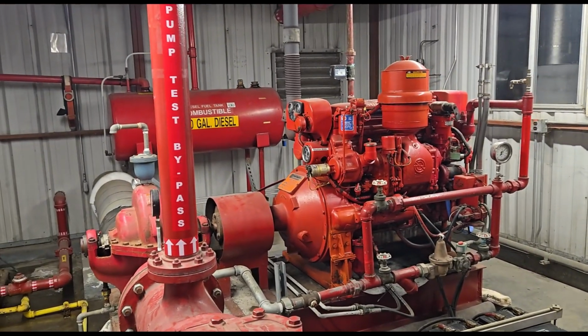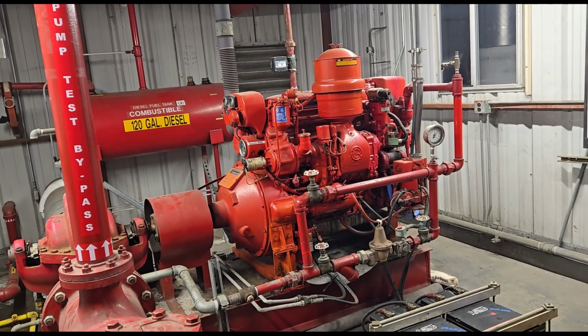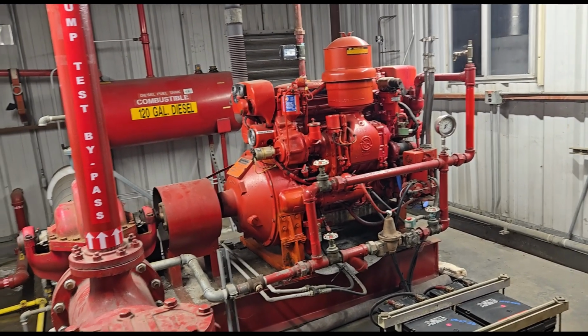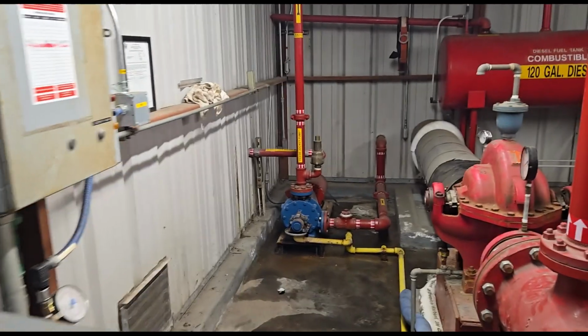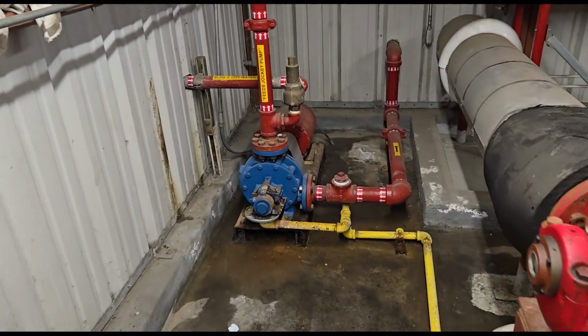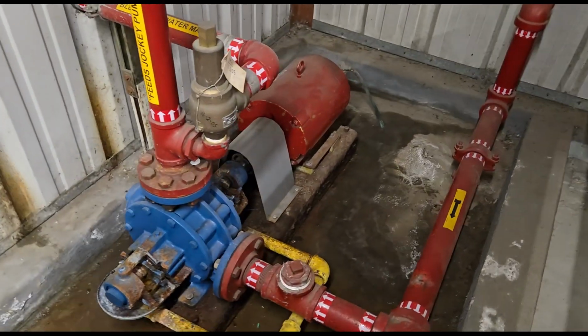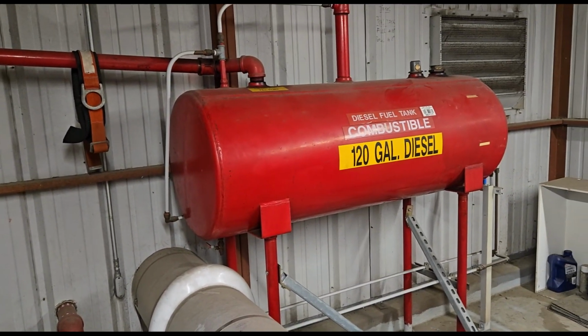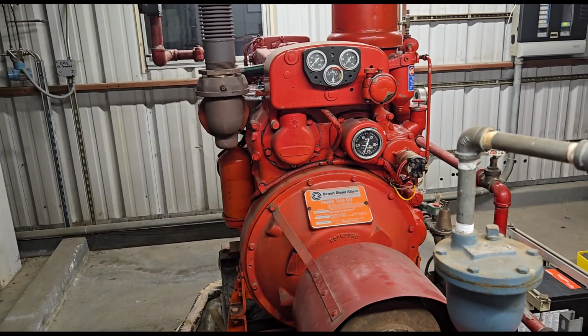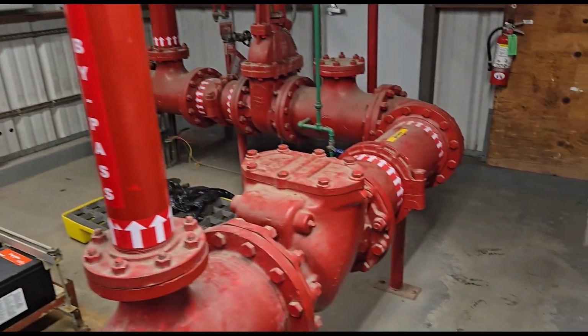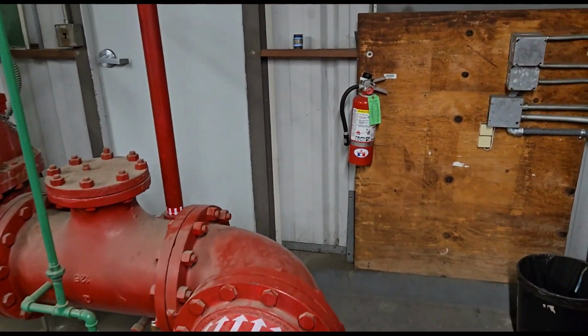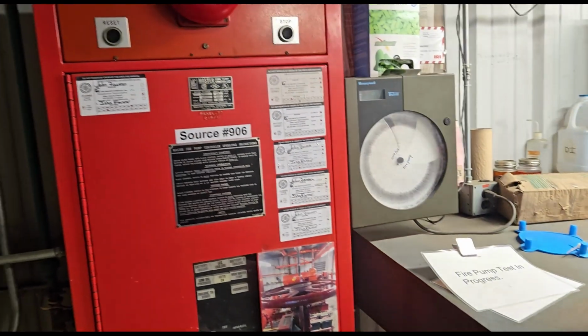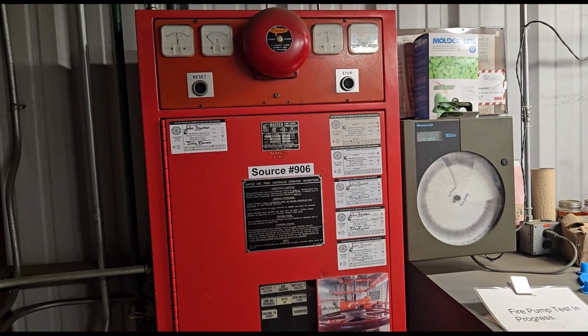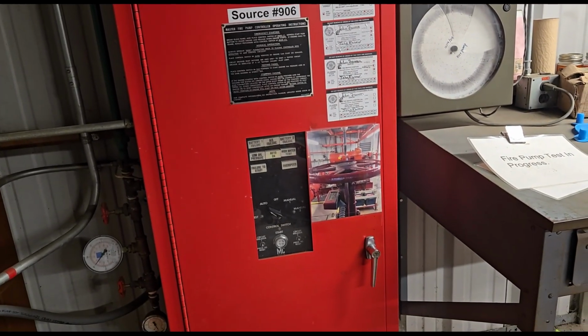So this system will be tested by a sprinkler technician or a sprinkler fitter. This client does not have my company as their contract for their sprinkler fitter side, so they have a separate company do that. The reason I'm going to bypass the fire pump is I don't want anything to turn on. I don't want any issues with the pump itself. I don't want the system to get over pressurized or the PSI get too high where it can pop the sprinkler head. So what we typically do is we simply bypass the fire pump by turning off the fire pump controller. That way we have no issues.